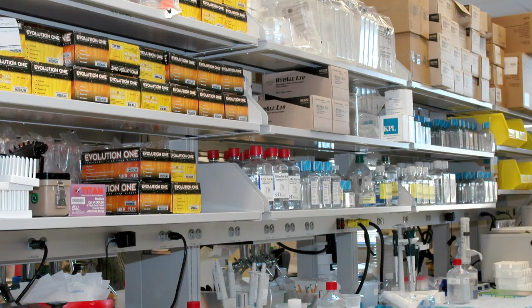Reagent receiving protocol. Reagent should be received by the lab as soon as it arrives at the purchase department. No delay is accepted, as most of the reagents are temperature sensitive. They have to be maintained in cold chain. Manufacturer's name, reagent quantity, lot number and expiry date should be recorded.